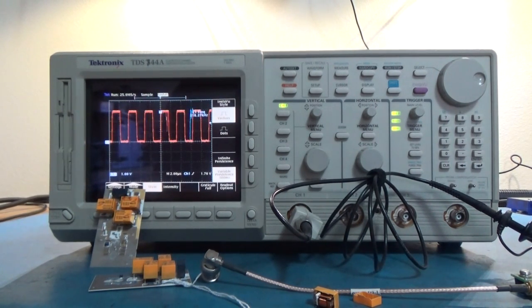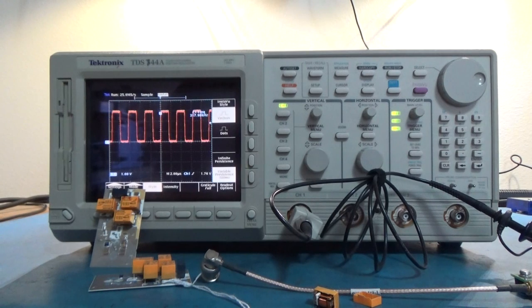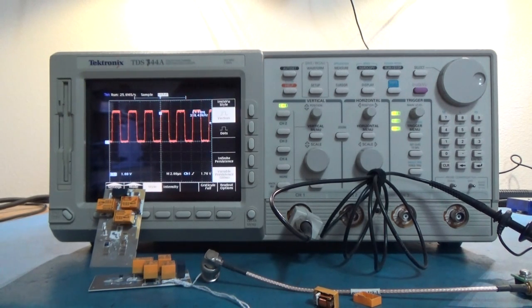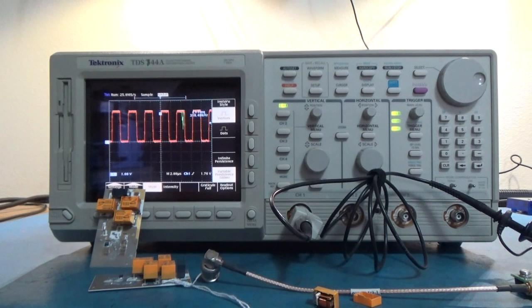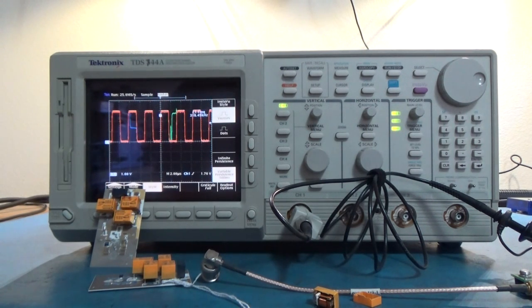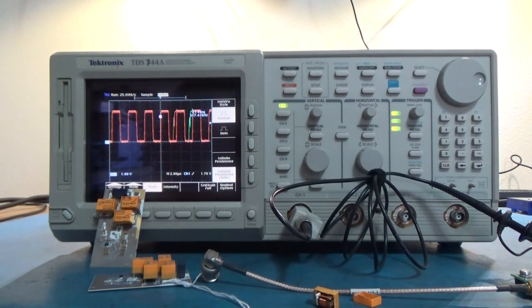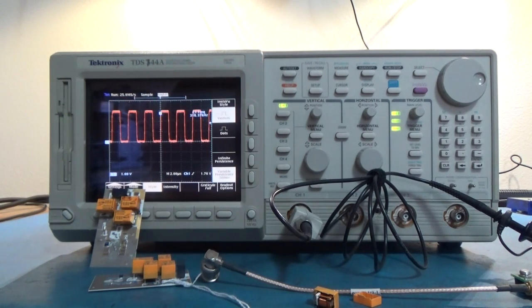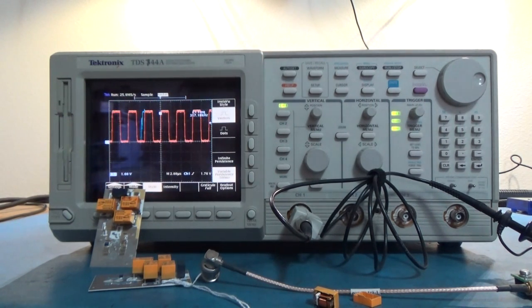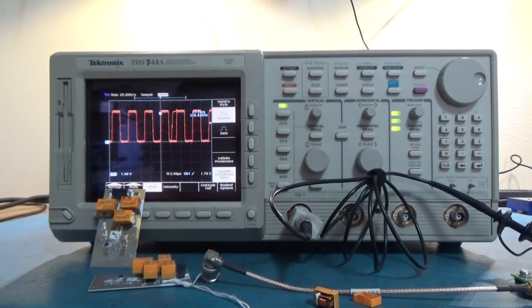The issue you can run into converting one of these to like a 784, is that even though all of the attenuators are 1 gigahertz rated, not all of them can be calibrated out that far. And it probably has to do with age. Who knows, maybe if you do the DeoxIT thing. Let me know if the DeoxIT thing works. At least do me the honor of posting a reply that works out of curiosity for me.